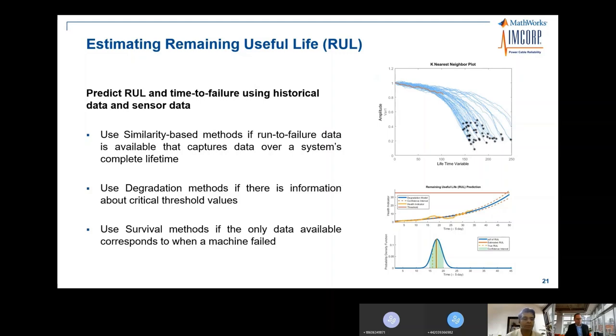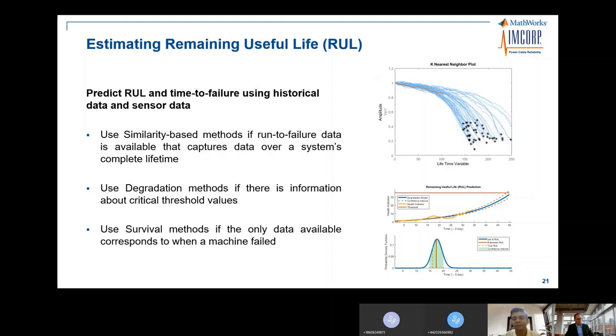Once predictive maintenance algorithms are built, you can go beyond predictive maintenance to identify the remaining useful life of equipment — knowing well in advance how much life remains so you can plan replacements ahead of time. To develop remaining useful life algorithms, multiple methods exist: similarity-based methods using run-to-failure data captured over a system's lifetime, degradation methods using threshold values, or survival methods using data from failed machines.